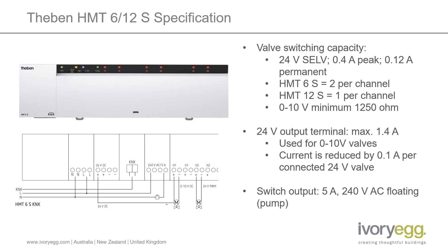Taking a more detailed look at the specification: each of the valve outputs is rated at 0.4 amp peak for the switch-on demand, and then 0.12 amp during runtime, powered from the onboard power supply. On the HMT6S, which has six channels, you can have two valve actuators per channel. On the 12S, you can have one per channel. But if needs be, you can always link together channels and the parameters to increase the number of valves per zone. If you are using it for 0 to 10 volt, the minimum resistance is 1250 ohms. And there is actually a 24 volt output terminal which you can use to power the valves, rated at 1.4 amps. And if you have a mixture of 24 volt and 0 to 10 volt valves, then you need to down-rate that output based on the number of valves at 0.1 amp per connected 24 volt valve.